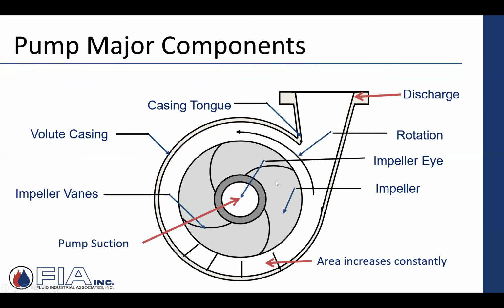This guy right here. So the impeller has vanes on it, and the vanes are engineered. They're there for a purpose based on flow, pressure differential, all of that, but they're adding velocity to the water, to the liquid as it enters. And the key is that the understanding is, you'll see this expression here, impeller eye. So there's an eye, and that's where the water enters. So in this orientation, that would be that suction, that end suction. That's the entrance. The water's entering into this eye of this impeller.